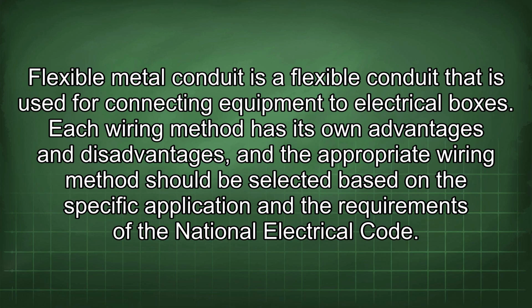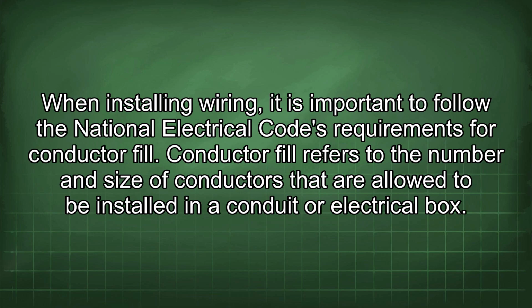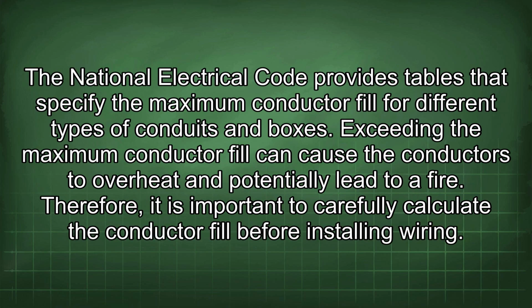Each wiring method has its own advantages and disadvantages, and the appropriate wiring method should be selected based on the specific application and the requirements of the National Electrical Code. When installing wiring, it is important to follow the National Electrical Code's requirements for conductor fill. Conductor fill refers to the number and size of conductors that are allowed to be installed in a conduit or electrical box. The National Electrical Code provides tables that specify the maximum conductor fill for different types of conduits and boxes. Exceeding the maximum conductor fill can cause the conductors to overheat and potentially lead to a fire. Therefore, it is important to carefully calculate the conductor fill before installing wiring.